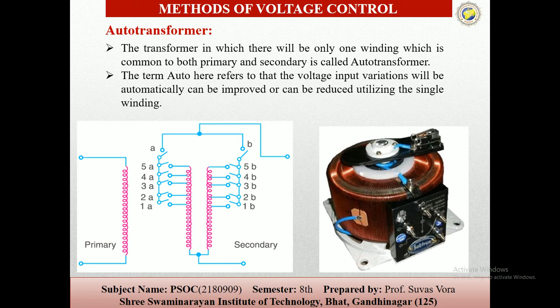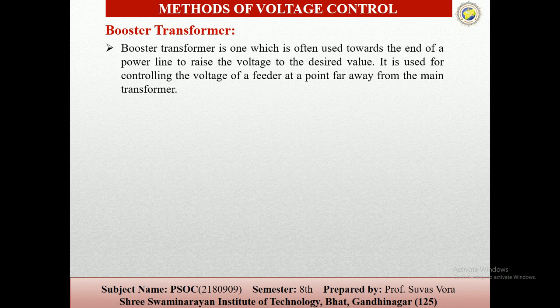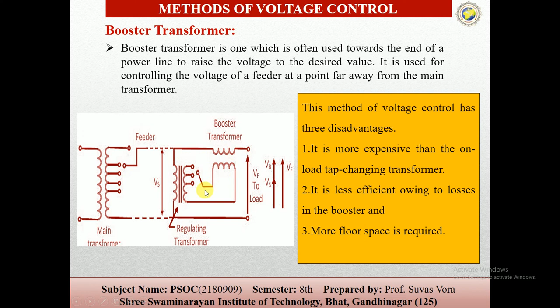The next one is the booster transformer. In the booster transformer, the secondary has a larger winding as compared to the primary winding, so the voltage on the secondary side is larger, and this value of the voltage is selected by selecting the proper tapping. So you can see that they have some disadvantages. The three main disadvantages are: it is more expensive than the other tap changing transformers, it is less efficient due to the loss in the boosters, and more floor space is required. You can see here, the tap is given on our main transformer, but we can have another transformer and the boosting systems.